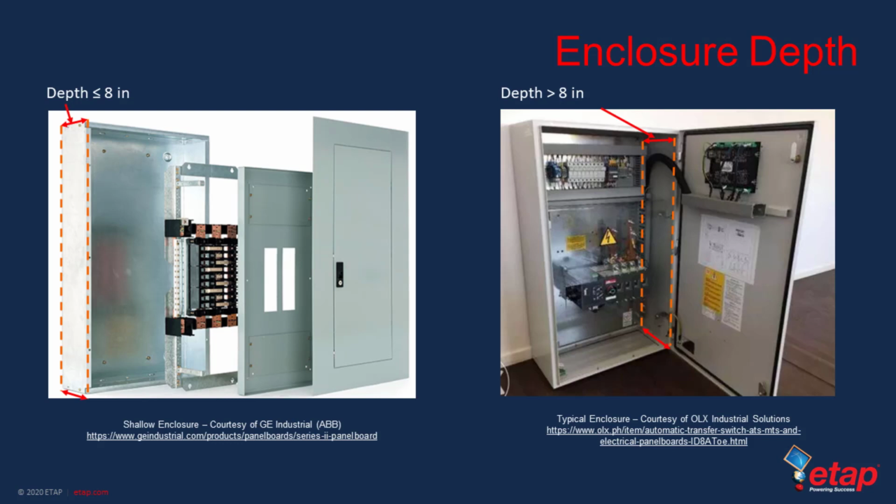In the previous images, we saw only examples of the width and the height of the opening area of the enclosures. In this particular example, we also see that the depth of the enclosures has a significant effect, in particular for low voltage equipment constructions. Also, if the variation of the depth is specified, the C area plots can account for the effect of the depth in the incident energy representation of our C area plots.